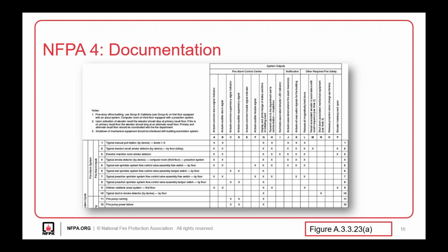If the original construction documents indicated that these smoke detectors should be included, then you just go ahead and create a corrective action to put those in the programming to actuate that smoke management. But if the construction documents don't include those detectors as a means to actuate that smoke management system, you're going to need to send that recommended remediation back to the original design engineer, who then will change the design documents, and then it will need to be approved again by the authority having jurisdiction.